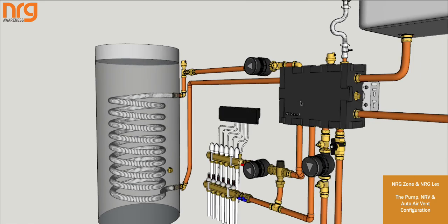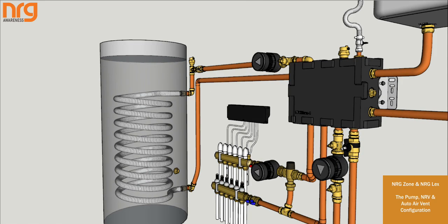When the pump leaves the manifold, it passes through a non-return valve and a vent. The reason for that is we want the air not to come back through the water that's in the coil when it heats, and at the same time, when the cylinder is not to be heated, we don't want drifting heat going over towards the cylinder, because you've got a very good incidental gravity loop potential here that could put heat into the water you might not necessarily want. So the non-return valve prevents that.